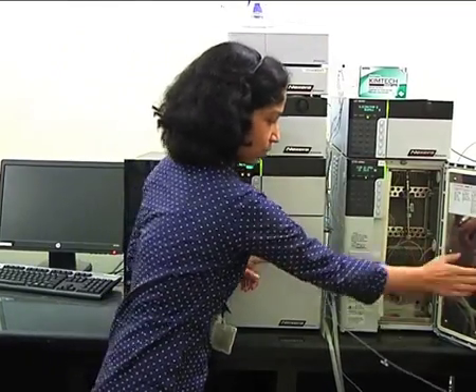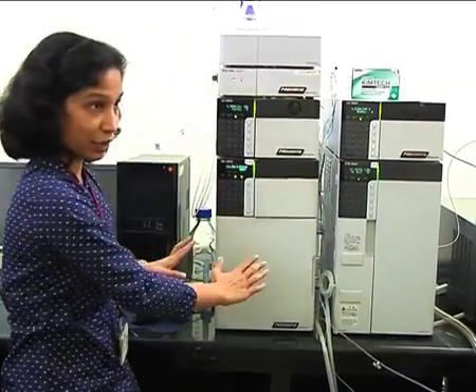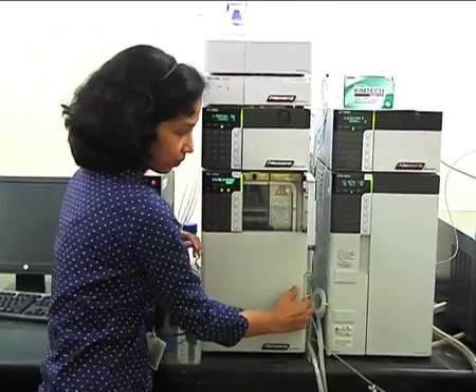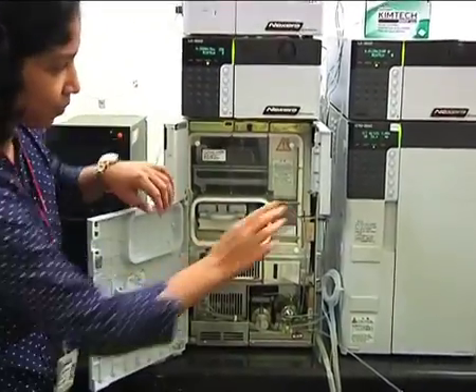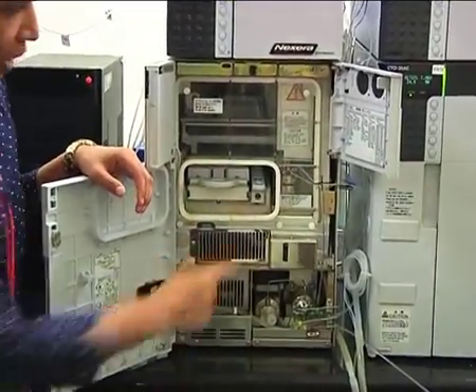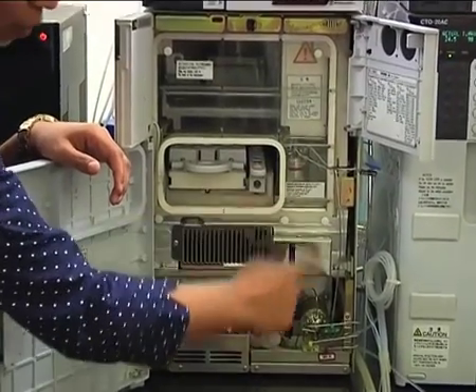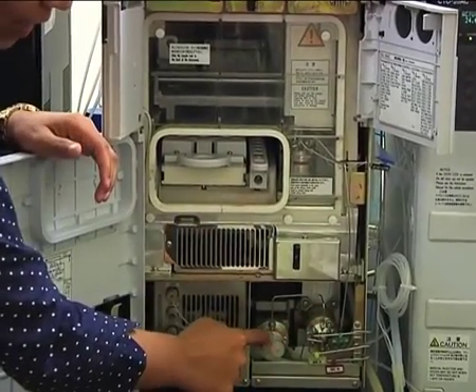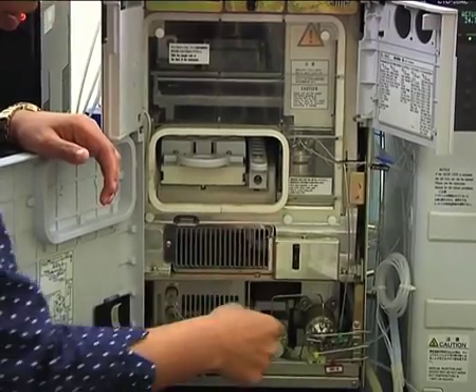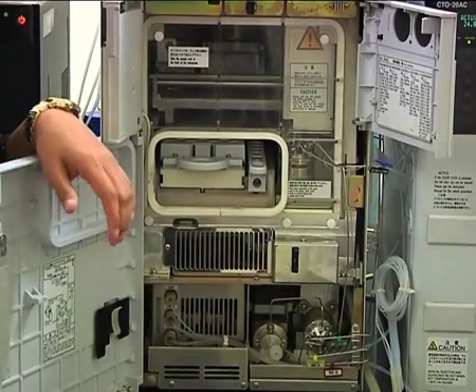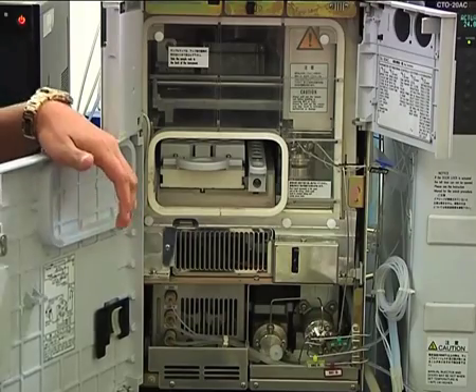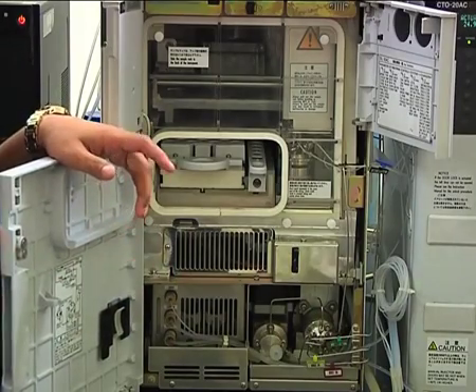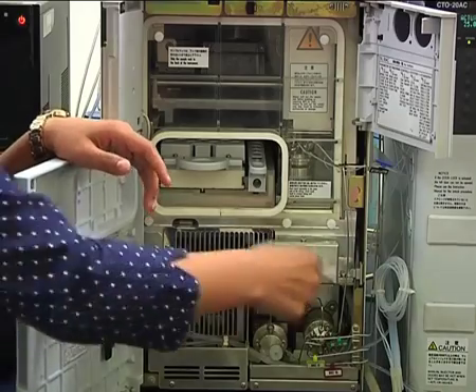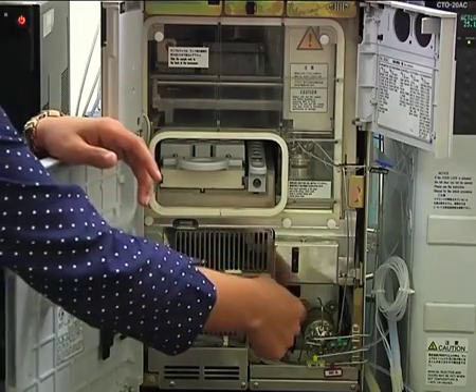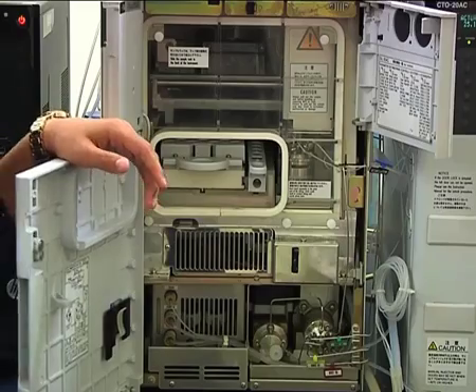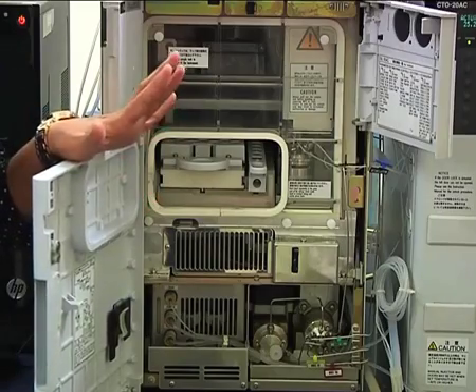This is the auto sampler unit. Any auto sampler unit, if you see, has 3 parts. One is the high pressure valve, one is the low pressure valve, and one is the measuring pump, or metering pump. What is the function of the measuring pump? Whenever you give a command to inject 10 microliter of sample, that is done by this measuring pump. It will inject 10 microliter or 5 microliter depending upon the command.